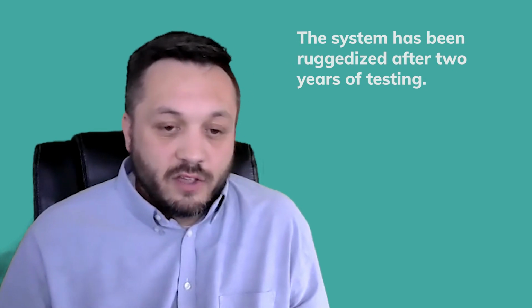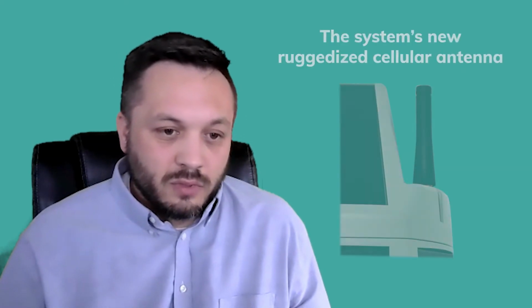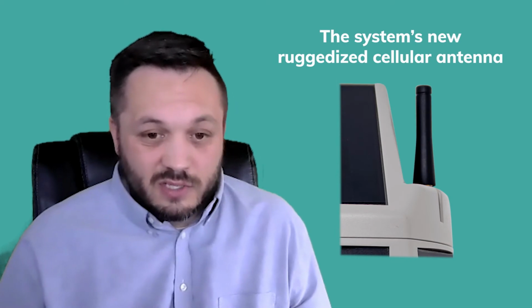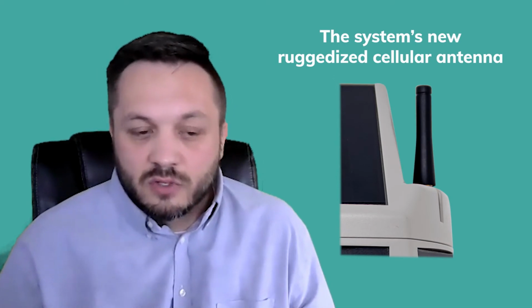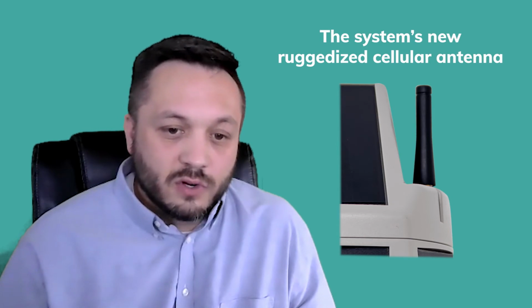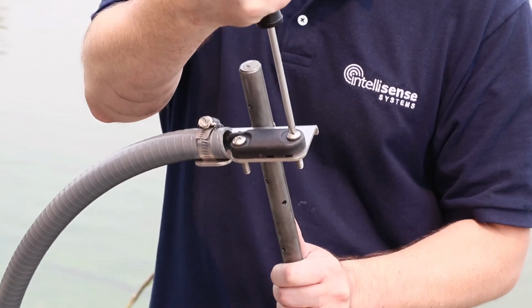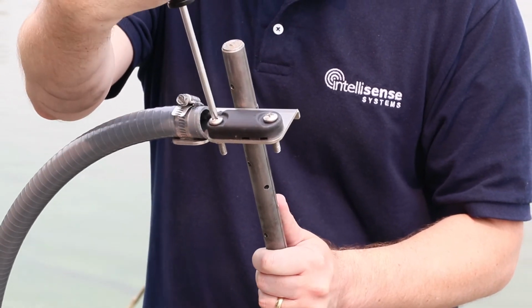The first was the cellular antenna. We initially used a flexible antenna that could be pointed to gain greater signal strength, but it wasn't rugged enough for the weather in Charlotte-Mecklenburg, so we had to come up with a new antenna. It's much more robust, and we also created a new bracket for the pressure transducer that was more rugged and could withstand more debris hitting it in faster streams. We also changed the power up and power down process in our cellular modems to minimize any potential premature failures.